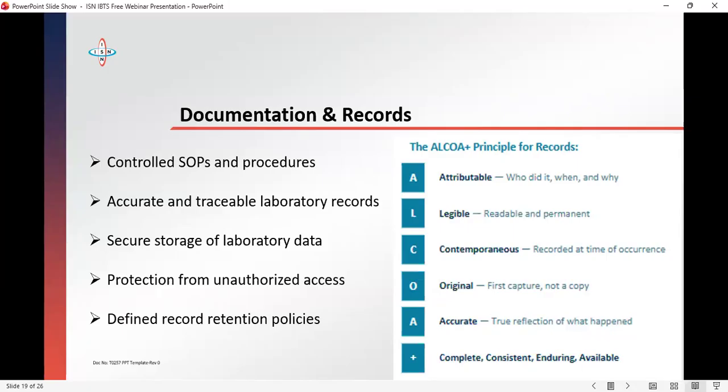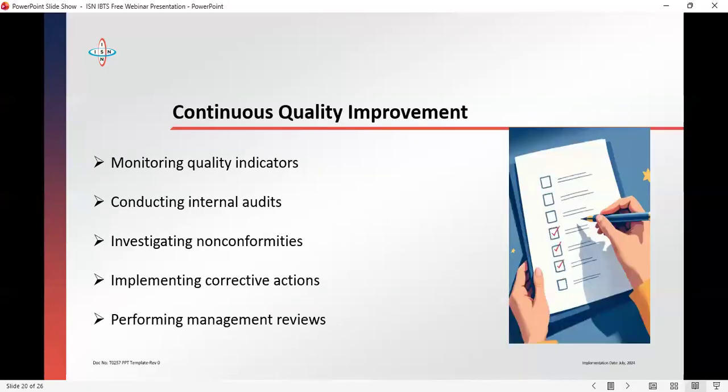If you have an SOP, everybody that is required to use that SOP must have access to it. It must be consistent. If it is to be used by everybody in your chain of laboratories, they must be using the same version. Not, I have the version of 2025, whereas we're in 2026. No, have a way of controlling it. And for everything that is extinct, you need to archive it and remove it, but still keep a record of it with your quality officer who has access to all the versions.